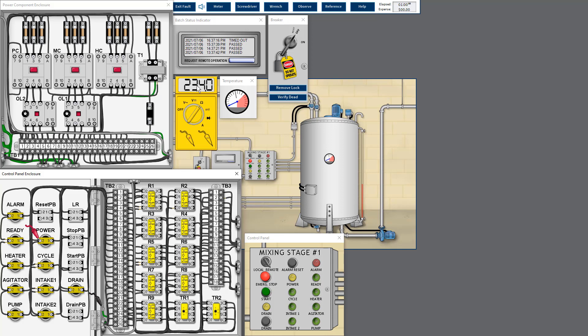Now I check the earth fault at the load: normalize the connections and open the point-two connections for each component one by one. The resistance remains the same, meaning there is no earth fault before the load or at the load. I will not continue checking after the load for this parallel circuit since I know it will be okay. Normalize the wiring connection.